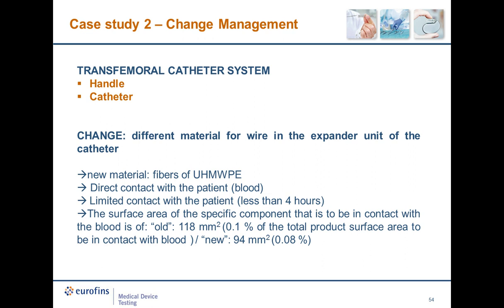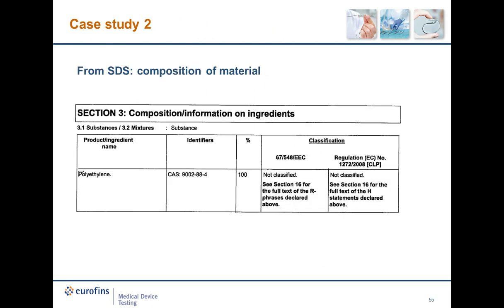The device is a transfemoral catheter system composed of a handle and an actual catheter. The change is related to the different material for the wire in the expander unit of the catheter. The new material is ultra-high molecular weight polyethylene, and for this material, there is a direct contact with the blood for a limited time. The surface area of the specific component in contact with blood is smaller for the new material compared with the old one.